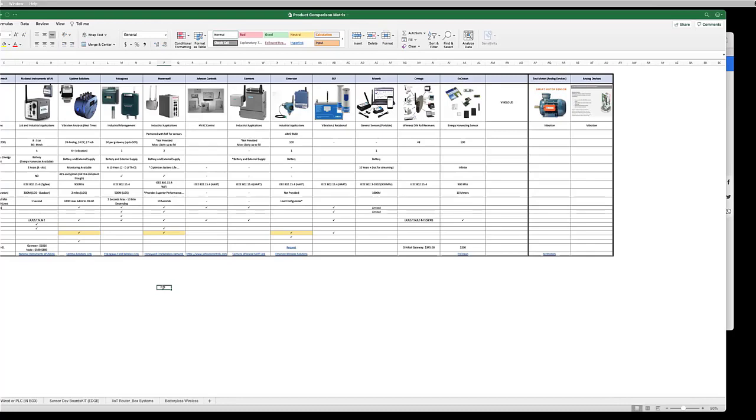But if you don't have that and you simply put a device in there and it's supposed to transmit all of the on and off transitions, and you have a whole bunch of these things all over the plant, then something inside of the gateway needs to be doing the counting and making sure that you didn't lose contact with your device and possibly lose counts.